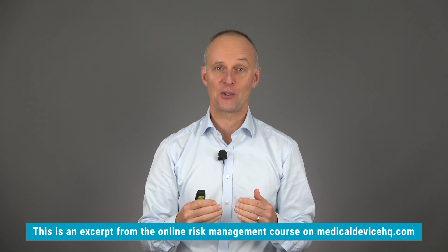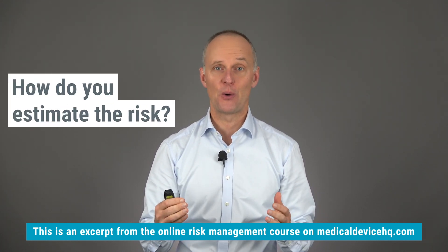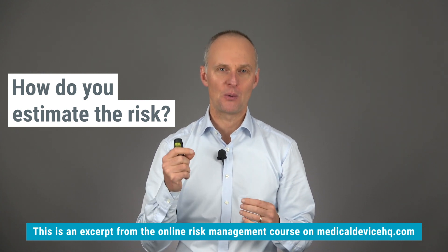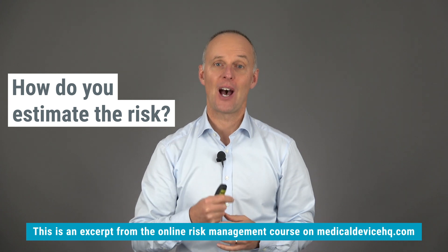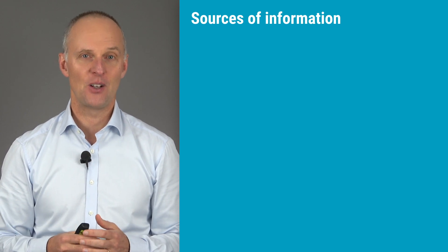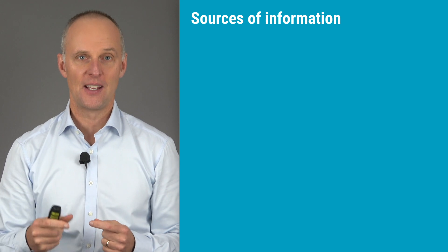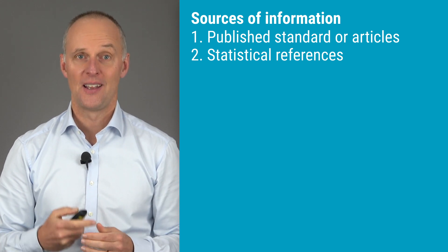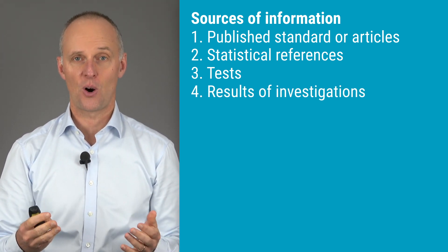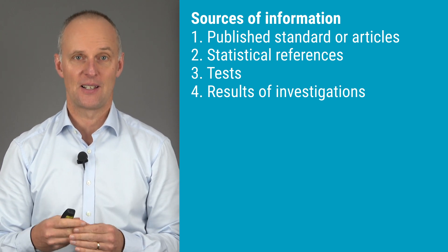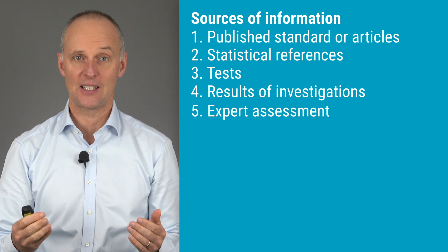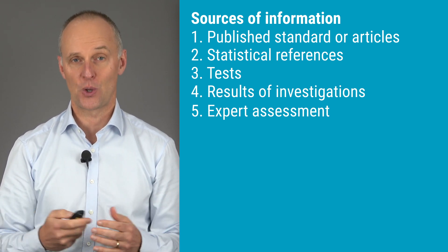Now we've talked about the basics of estimating risk. One of the most common questions I get during my training courses is: how are you supposed to estimate the risk? Let me tell you how it's supposed to be done in the perfect world. When you estimate the risks, you should ideally be finding information from the following sources in order of priority: published standards or articles about similar devices; statistical references to products already on the market; tests that you do to explore risks; results of investigations and analyses — this could be calculations, Monte Carlo simulations, or fault tree analysis; and expert assessment, for example when consulting internal or external experts on how often things would go wrong.